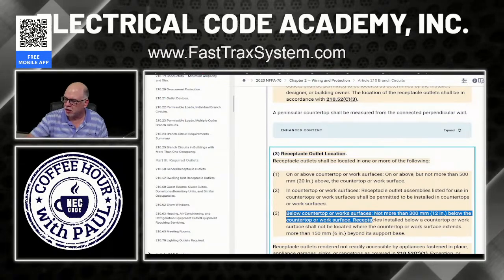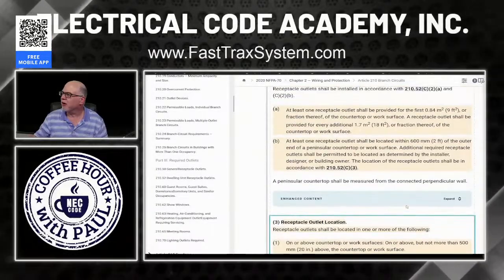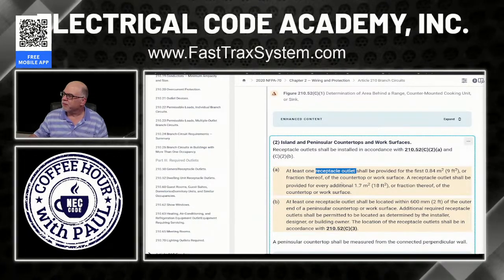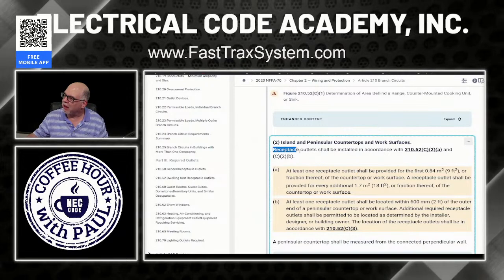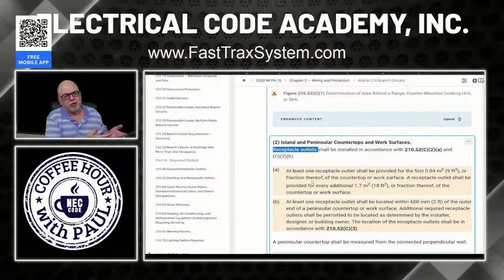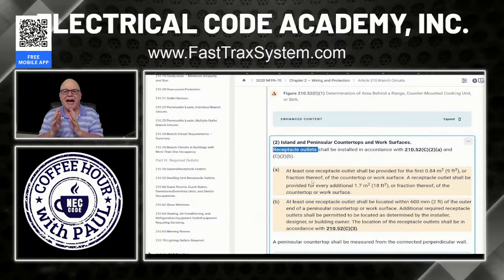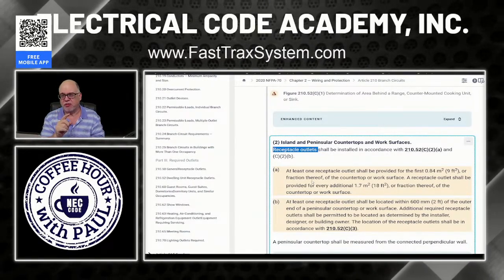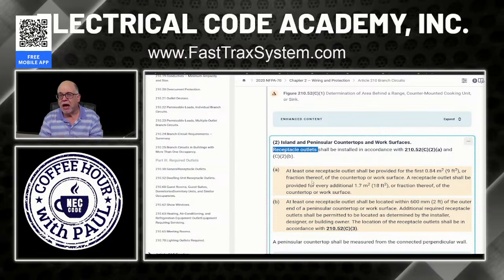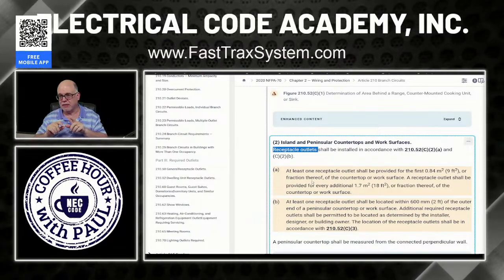And so when you go back to the code, oh, wait a minute. I've got to point something out. Notice right here, it says receptacle outlet. Here, notice it says receptacle outlet. Why is that significant? Because the course talks about receptacles because that's what you're going to put in there. That's common sense. But I want to teach you something today. The receptacle outlet is the box, not the device. The box. Important. A two-gang box is two receptacle outlets because you could put two devices in it.